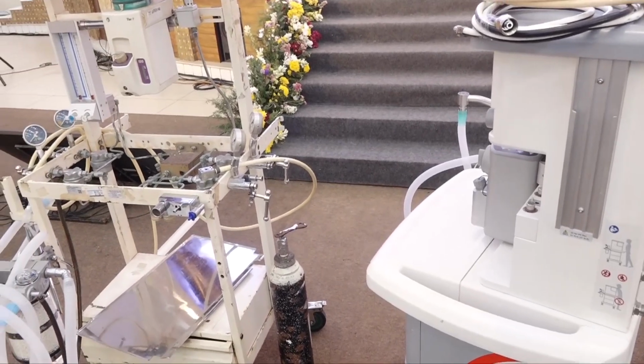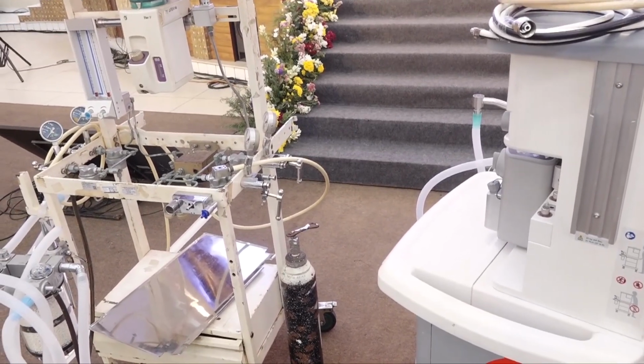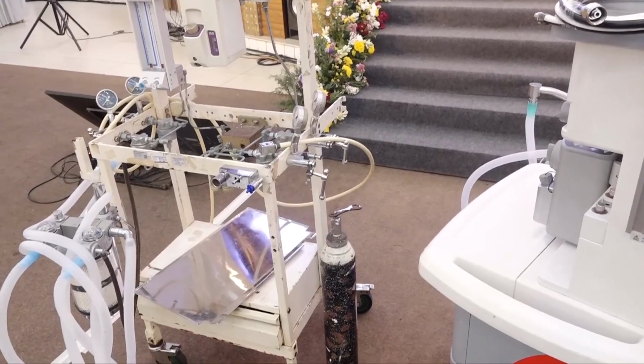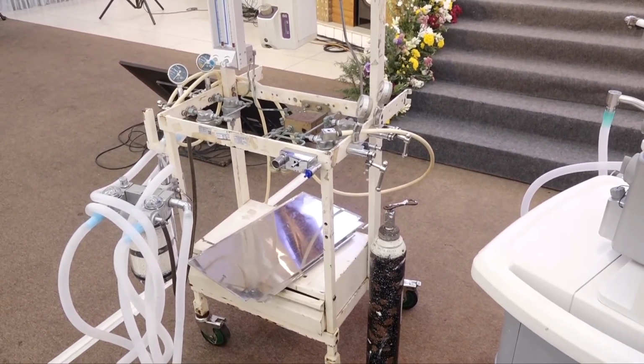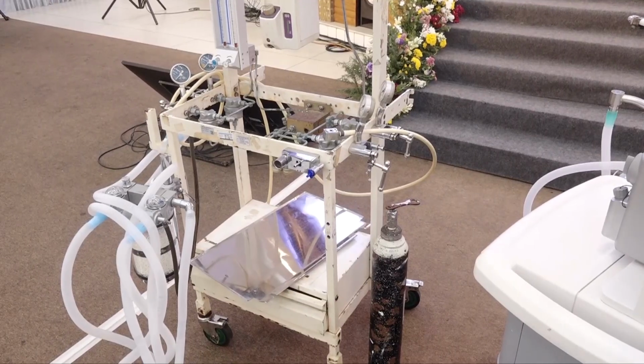So you come, open the oxygen cylinder and see if enough pressure is there for you. Whenever suddenly the pipeline oxygen source gets exhausted, you have to open this. So that's how you'll have to check it and close it immediately. Suppose, let us say, that you forget to close the cylinder after opening and checking.